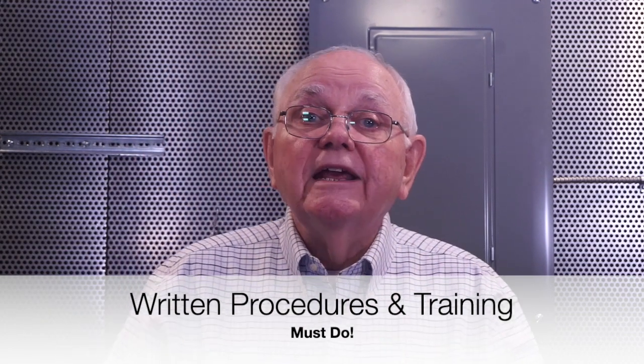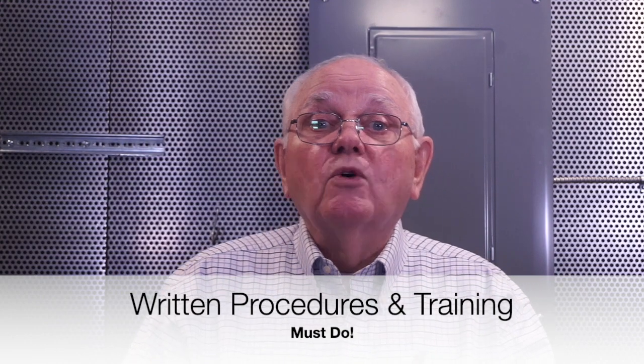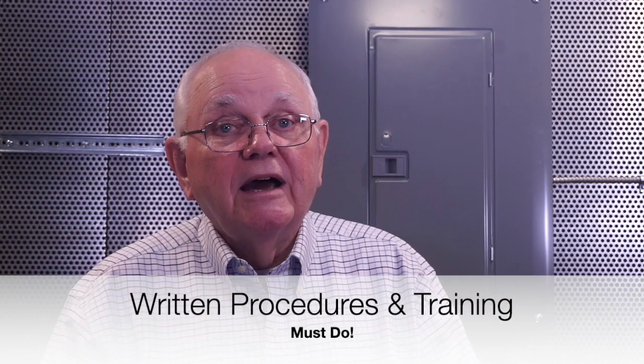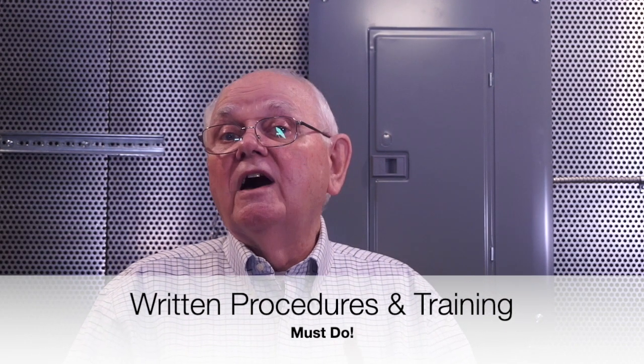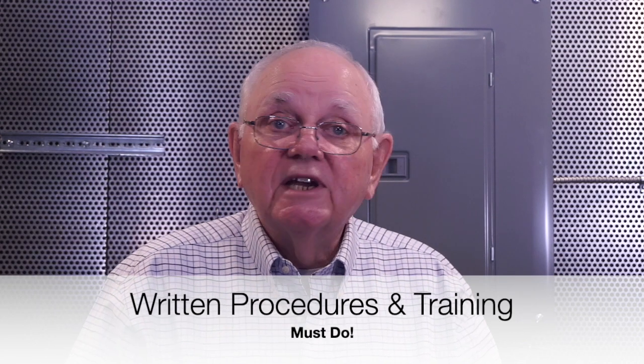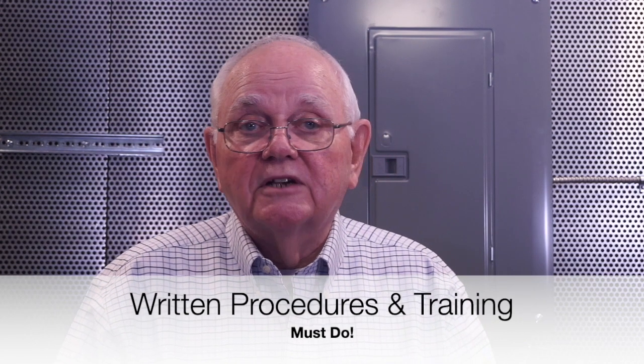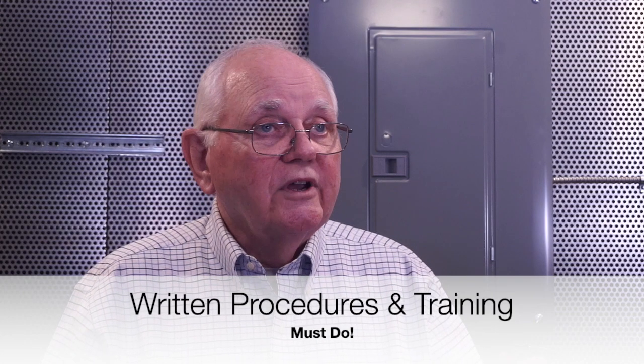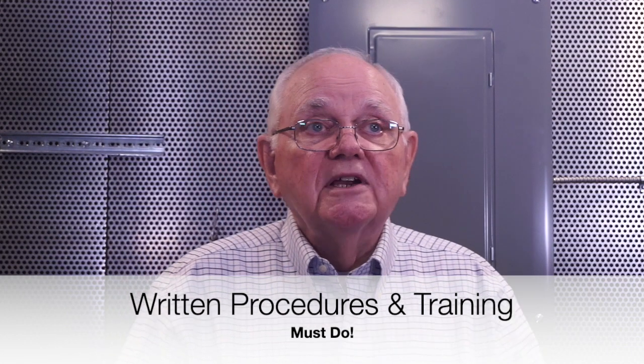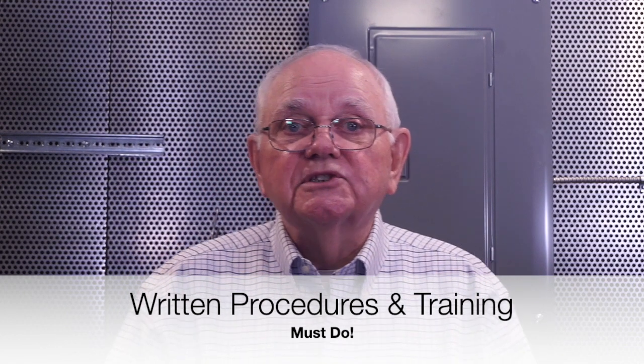As far as training, we've got to pay attention to qualified persons — what they have to be trained in and qualified in. You've got to follow all your safety requirements when doing electrical equipment maintenance. If I'm doing a high pot test, I may be raising the voltage on that 4160 switchgear to significantly high voltage levels, so I better keep all unqualified people away, establish that limited approach boundary, set up barricades, and make sure nobody gets a shock.